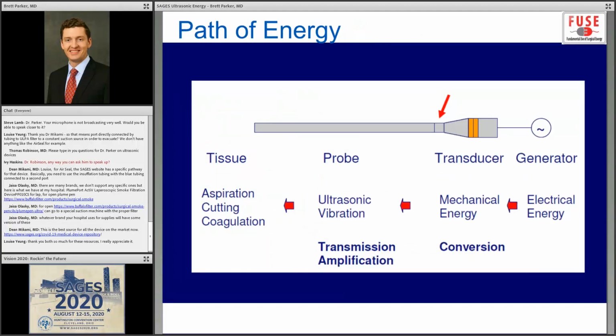So this is an overview of the mechanisms we've already described. Starting on the right side of this diagram, you have the generator, which again receives electrical energy either from AC wall current or direct current from a battery. That electrical energy is sent to the transducer, which excites the piezoelectrodes and converts the electrical energy into mechanical energy, which is transmitted down the probe or the shaft of the instrument and ultimately to the tissue through the straight jaw of the dissecting blade.